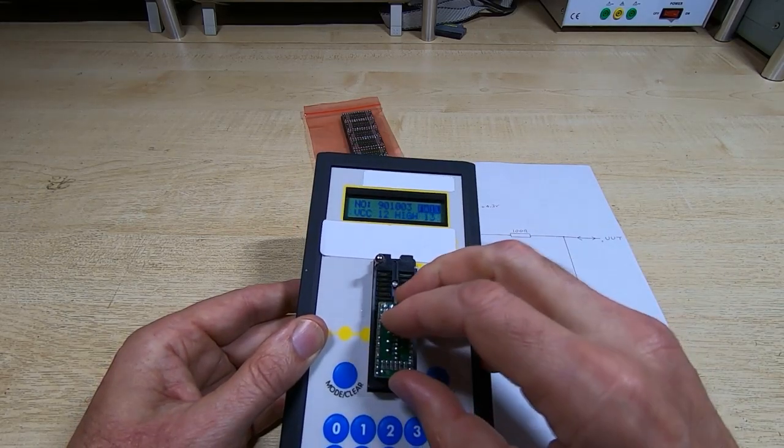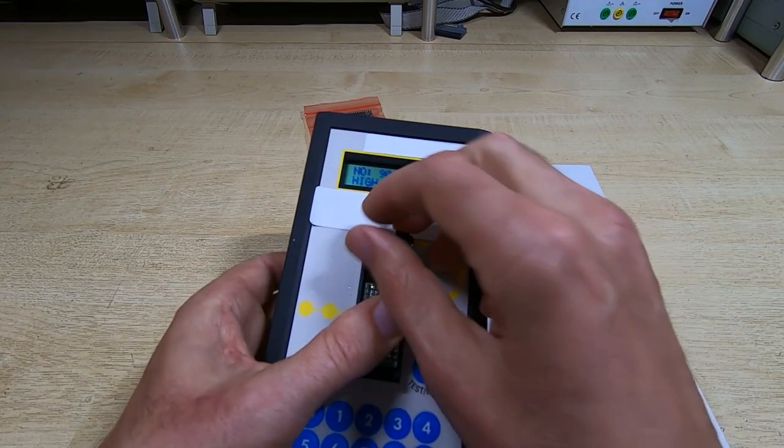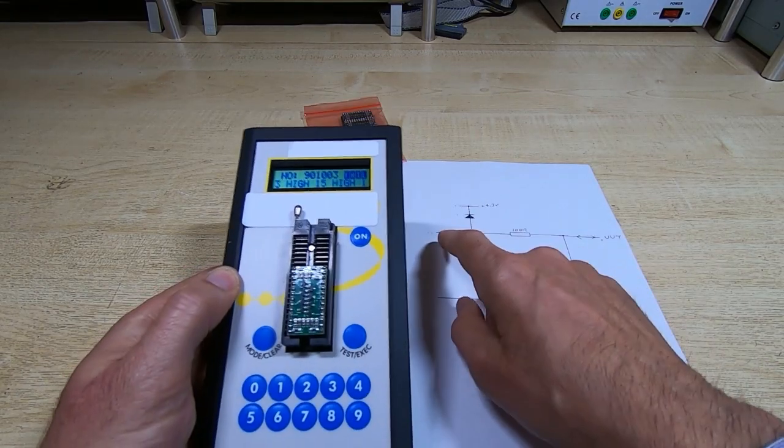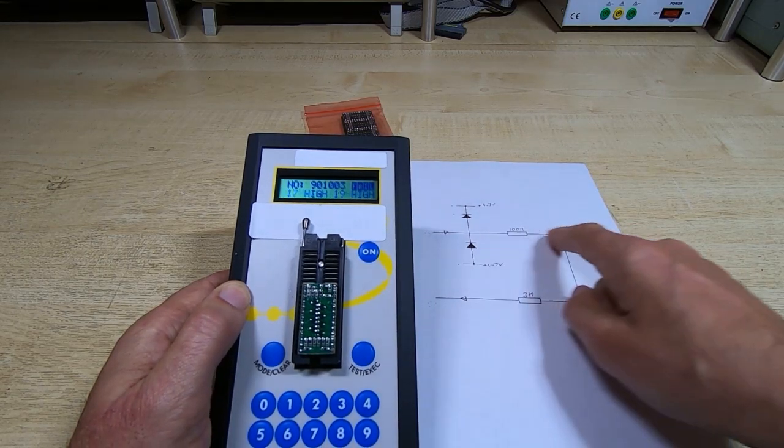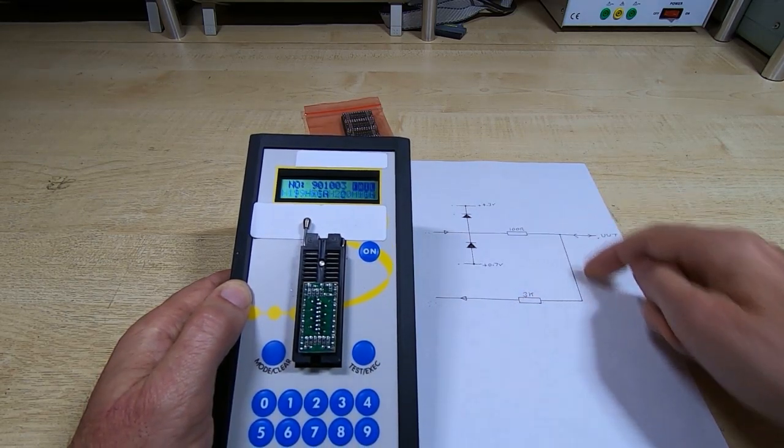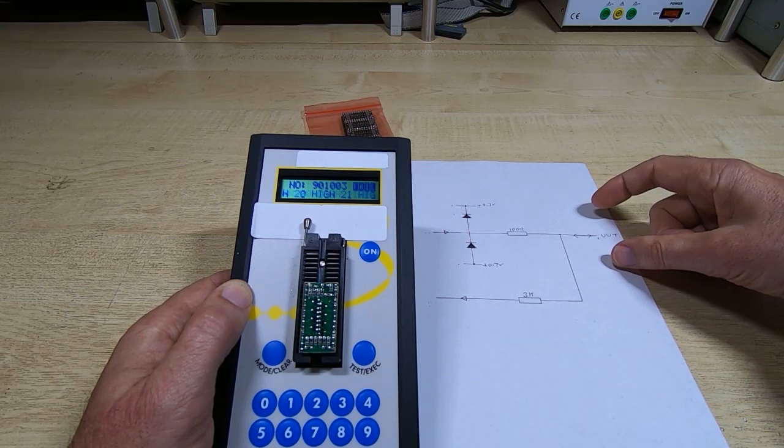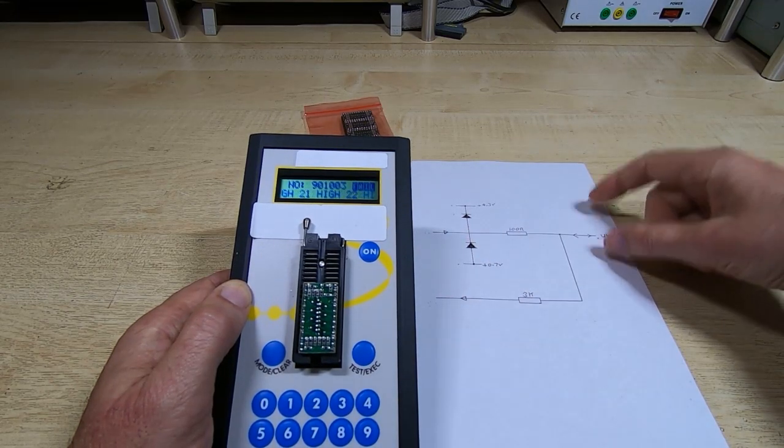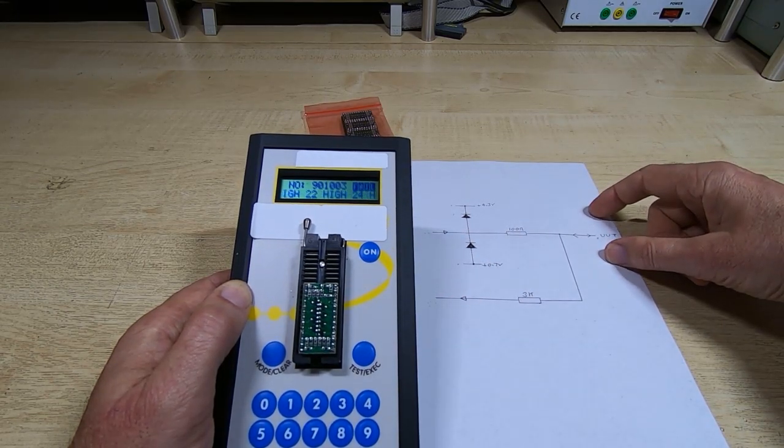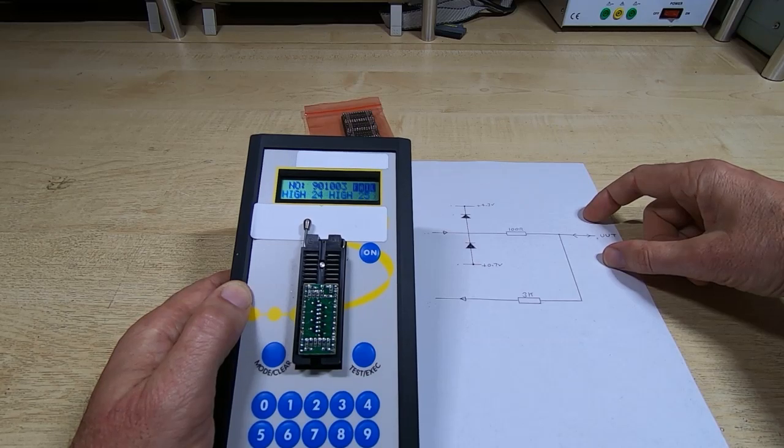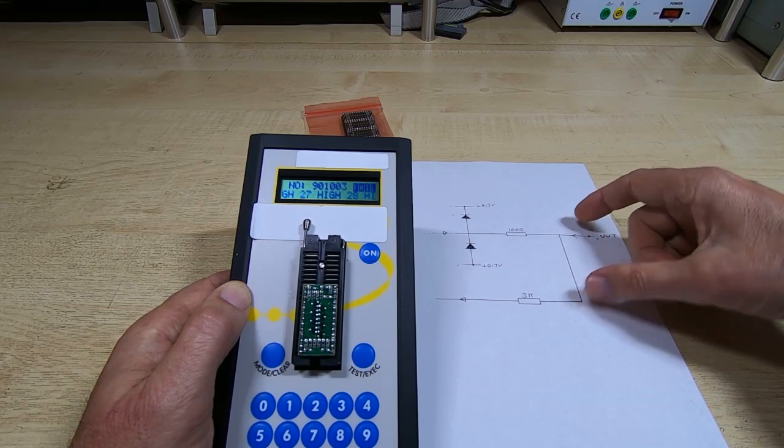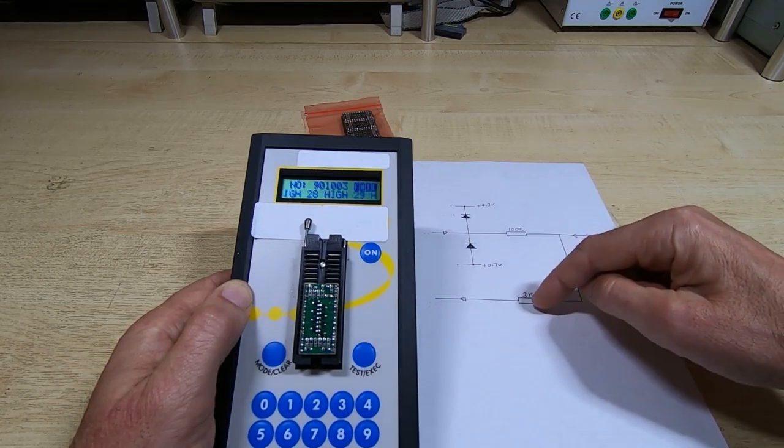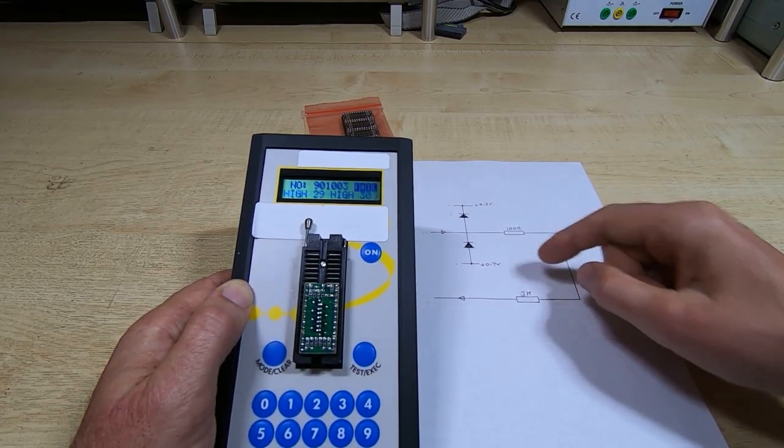I'll now take a module and plug it in, making sure I've got it the right way up. It's not just testing if it's conductive, because we've got resistors here - we know there's going to be a voltage drop. I've got the test set up so you can specify the voltage for the pass or fail. It's set up for a very tight tolerance, about 0.1 volts.